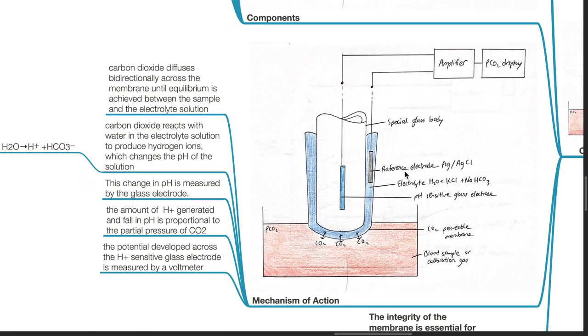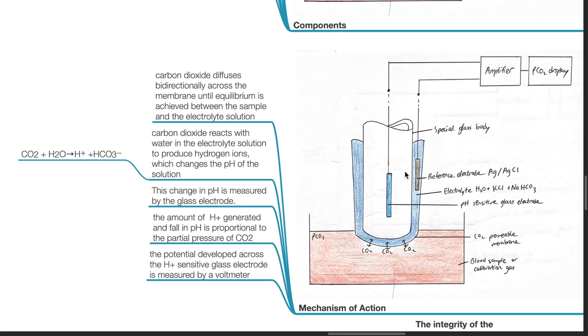Carbon dioxide diffuses bidirectionally across the membrane until equilibrium is achieved between the sample and the electrolyte solution. Carbon dioxide reacts with the water in the electrolyte solution to produce hydrogen ions, which changes the pH of the solution: CO2 plus H2O becomes H+ plus HCO3-. This change in pH is measured by the glass electrode. The amount of H+ generated and the fall in pH is proportional to the partial pressure of CO2. The potential developed across the H+-sensitive glass electrode is measured by a voltmeter.